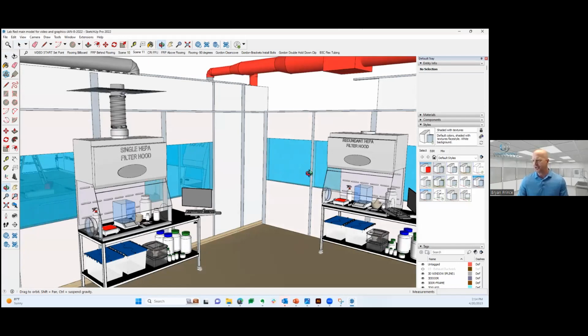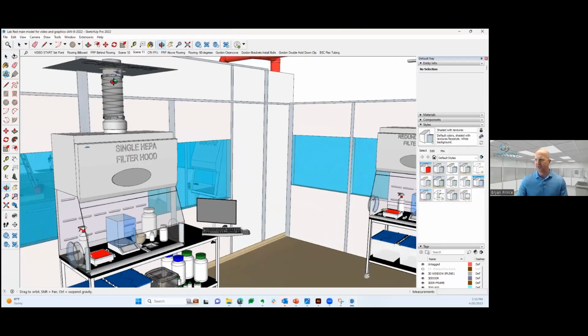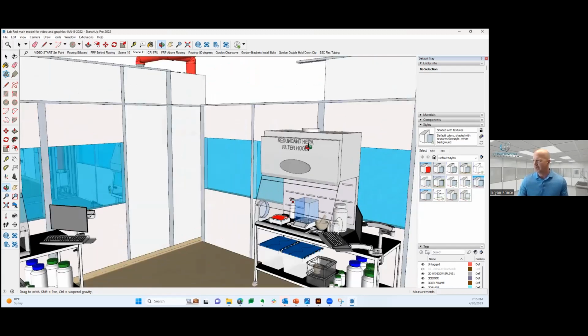This is a single HEPA hood that is externally connected, so you have to have that trunk. This is probably what the state board is going to be looking for - this trunk line connection. What they don't understand is that if it is a redundant HEPA, I don't need that trunk line. It can actually recirculate back into the space.